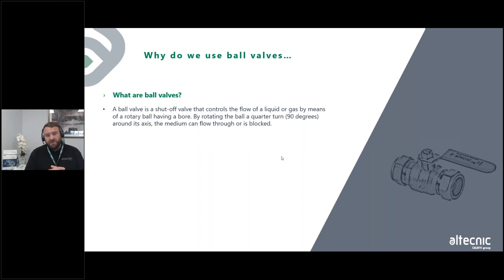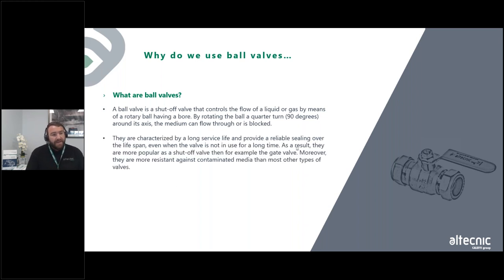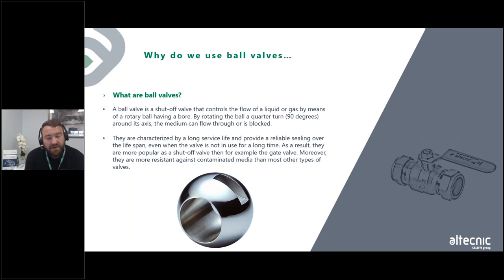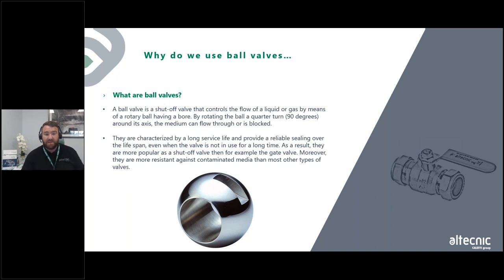Some people use ball valves for restricting flow, but their primary use is for isolation — to be fully open or fully closed. They're characterized by long service life and provide reliable sealing over their lifespan, even when the valve is not in use for a long time. As a result they are far more popular as a shut-off valve than, for example, a gate valve, and they are more resistant against contaminated media than most other valve types.